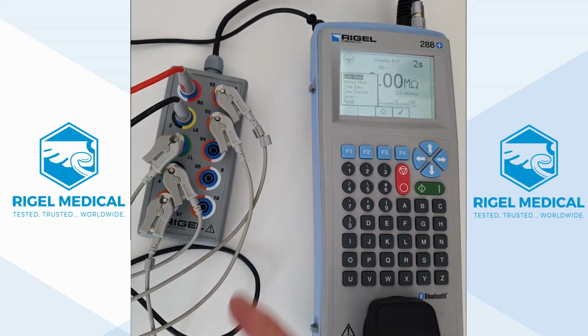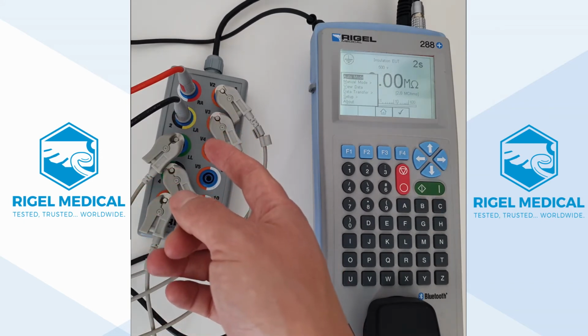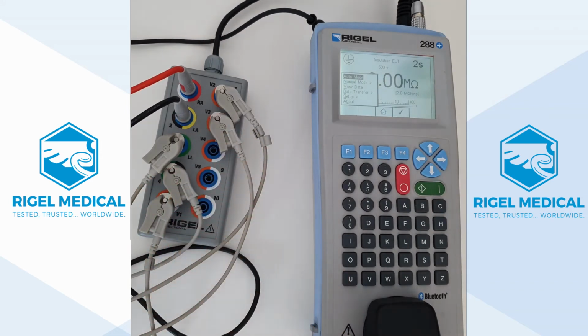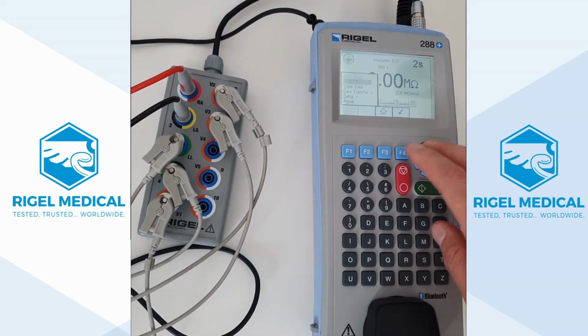So let's say our defib paddles are BF, defibrillator proof, and our ECG connections are CF, also defibrillator proof. However, in regards to safety testing, B, BF and CF are all that's relevant. The defib proof classification doesn't really apply.